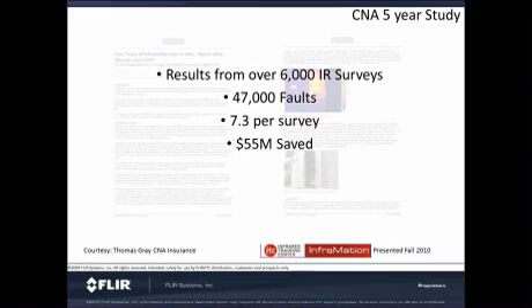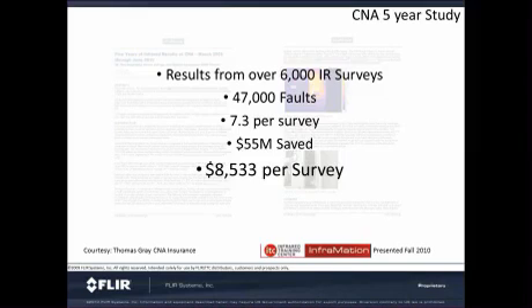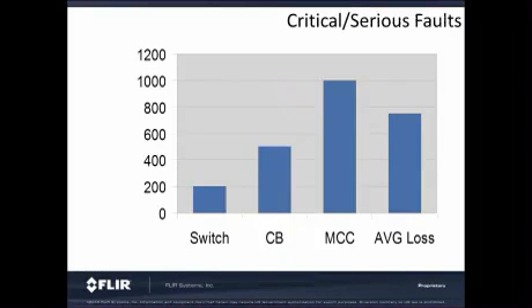Their surveys saved their customers $55 million in replacement costs. That is the cost to replace the product or the part that was about to fail. This works out to $8,500 per survey. As you can see, the average sale price of a thermal imaging camera is generally below $8,500. Therefore, you could pay back your camera within 1 year. What also is nice, and what they also found, was almost half of the surveys had one critical fault, greater than 75 degrees Fahrenheit. These are the problems that are most likely to fail catastrophically.